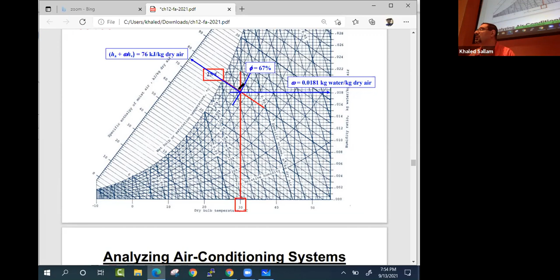So remember the cooling tower we talked about last time, and how it can lower the temperature of the water. I told you how much it can cool you down: not just to the dry bulb temperature, it can cool you down to the wet bulb temperature. If the air has room to get more water vapor, it can drop you to the wet bulb temperature. That's what you lose if you say you don't want to lose any water in the cooling tower and make it a closed system, turning it into a radiator like in a car. Then your limit is the dry bulb temperature; you cannot reach the wet bulb temperature. The only way to reach the wet bulb temperature is to put water in the air and lower the temperature.